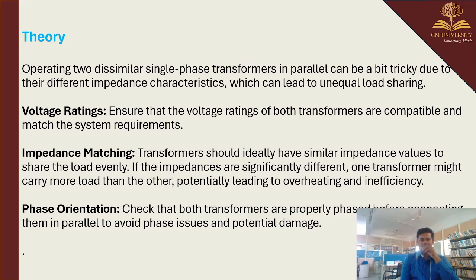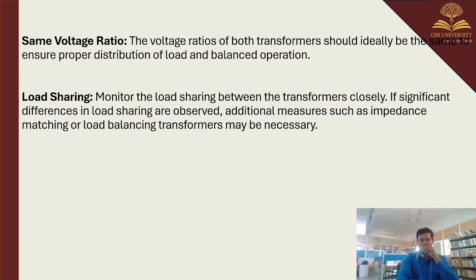Next, the phase orientation. We have to check that both transformers are properly phased before connecting them in parallel, to avoid phase issues and potential damage to the transformers. Next, the same voltage ratio. The voltage ratio of both transformers should ideally be the same, to ensure proper distribution of the load and balanced operation. Next, load sharing. Monitor the load sharing between the transformers closely. If a significant difference in load sharing is observed, additional measures such as impedance matching or a load balancing transformer may be necessary.